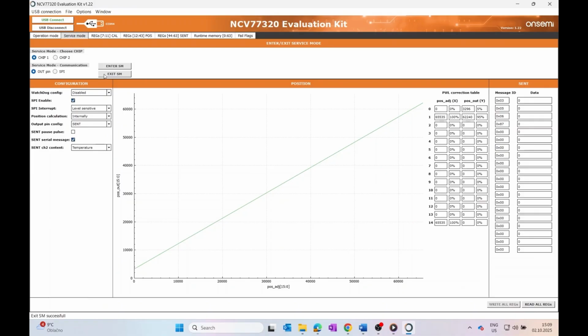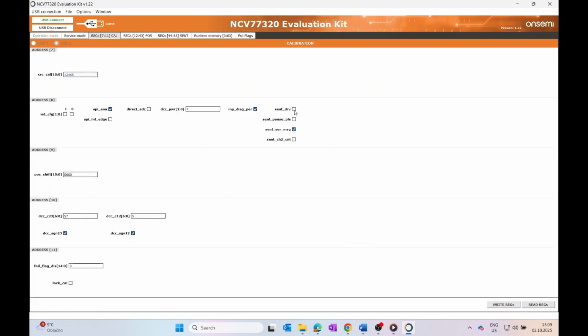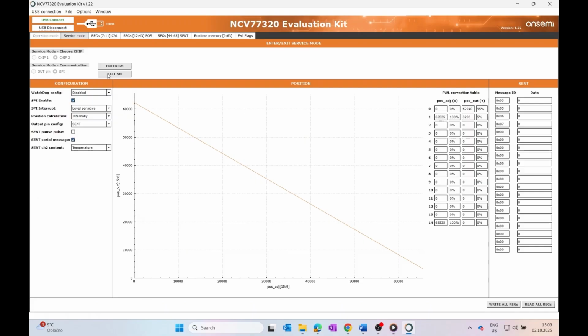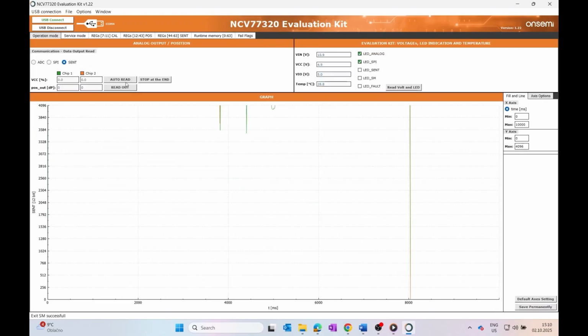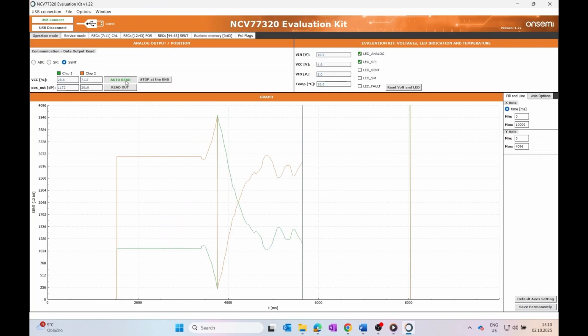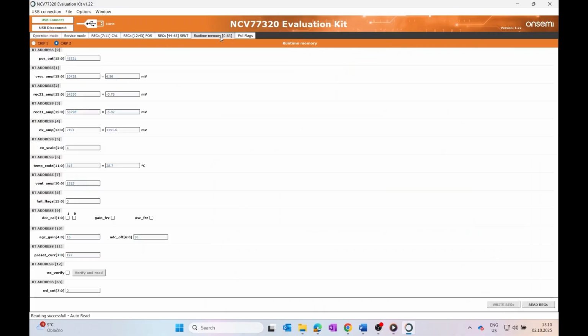For the second chip, we can now use the SPI interface to enter the calibration mode. Another possibility to select SENT output is to navigate to the detail register map and enable the SENT driver by setting the appropriate bit and pressing the write button. The device is now configured for SENT output, so now we can exit the service mode and return to operational mode to check the sensor output. Useful runtime registers can be read in operational mode via SPI. If SPI isn't available, they can be accessed through the output interface in service mode.